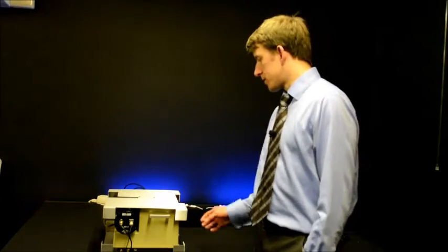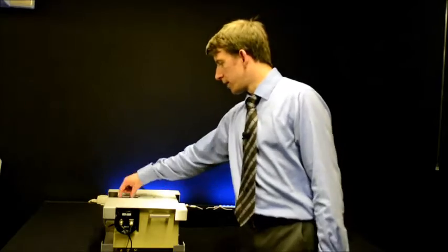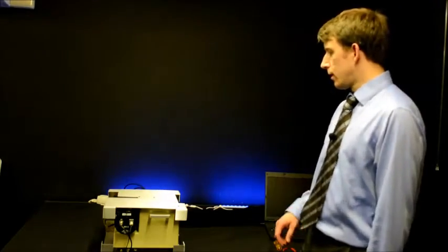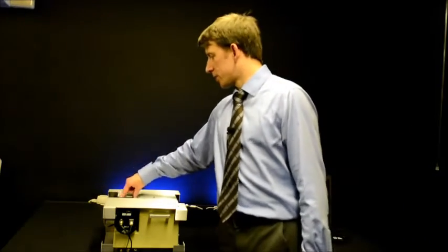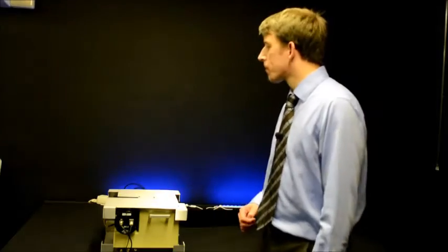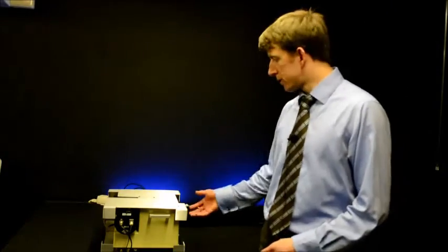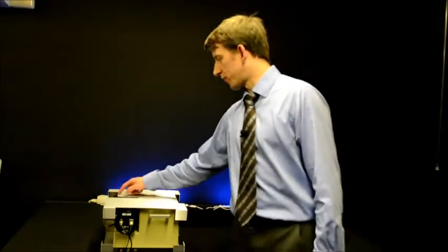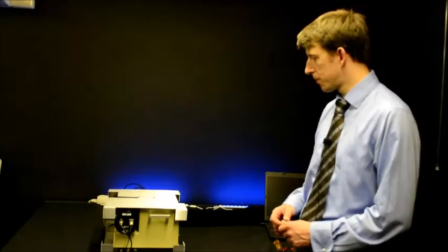The bandwidth of the system is defined by the largest of the entrance or exit slits. One can think quite clearly in the description of how this can be defined by the exit slit, in that, given that having obtained dispersion and the input light is dispersed to its component wavelengths, one can effectively consider the exit slit as the wavelength scale. The larger the slit, the more wavelengths one samples at a time.